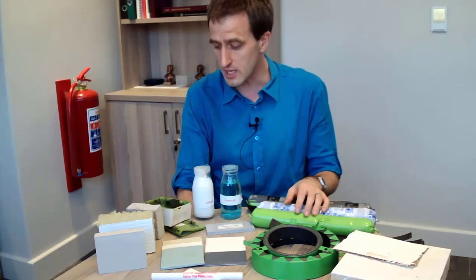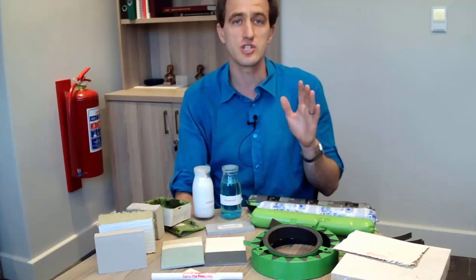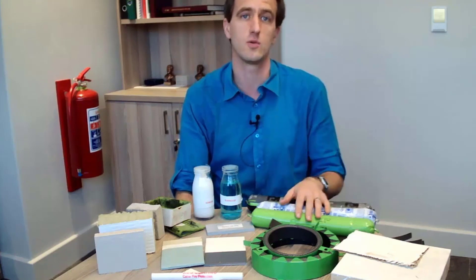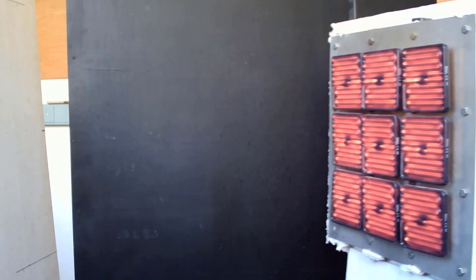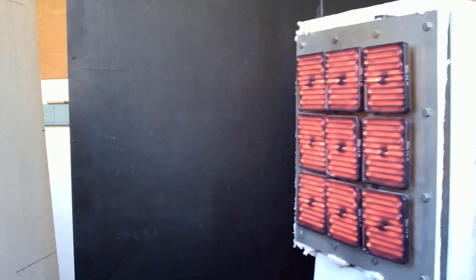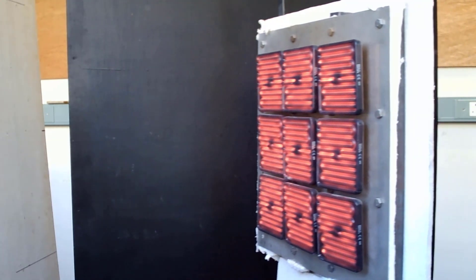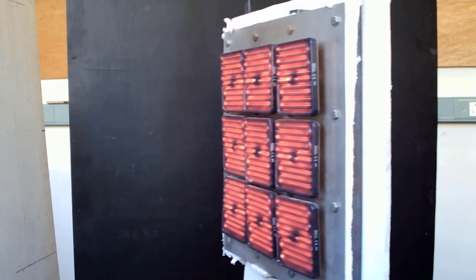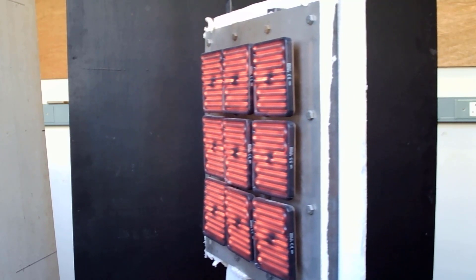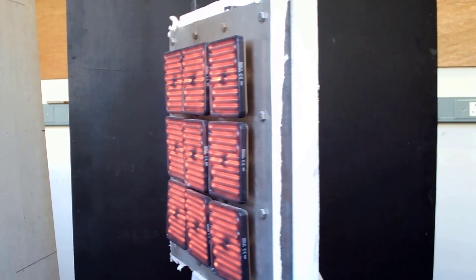That gives a brief overview of some of the products — there's a large number of systems available, so get technical advice and make sure you have proper specifications. Now that you've seen the products, we're going to test them on our HIRIS — a high-intensity radiant panel going to about 900 degrees Celsius, built by a student. You're going to see what happens when these products are subjected to high-intensity heat fluxes. This is not official testing; it's purely to show you what happens.